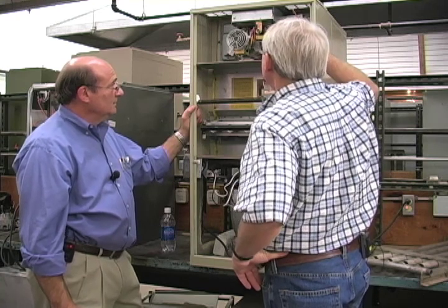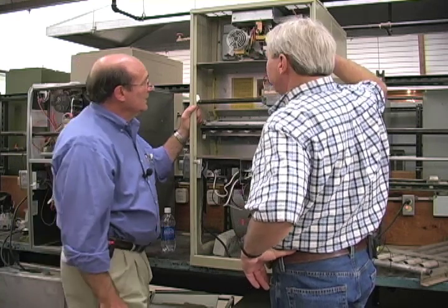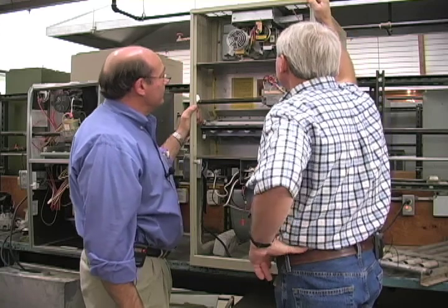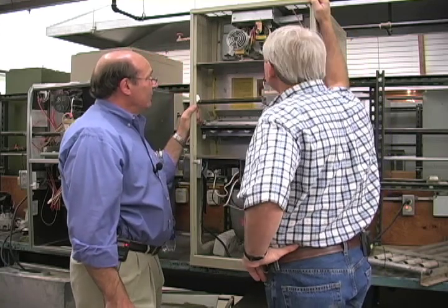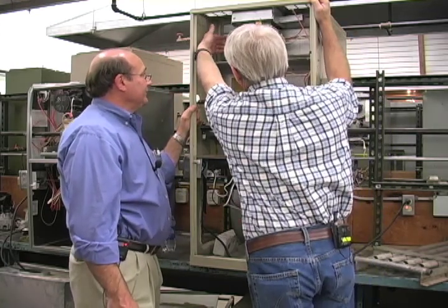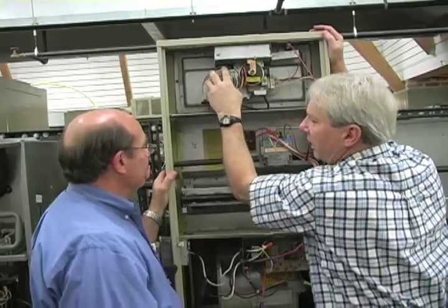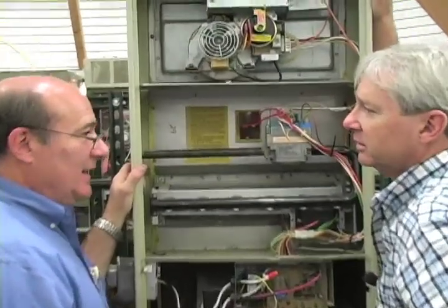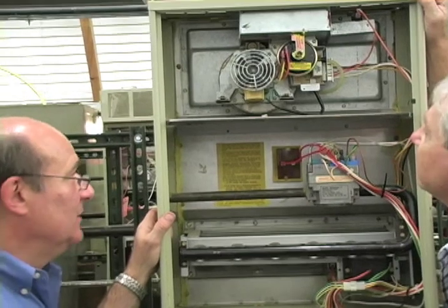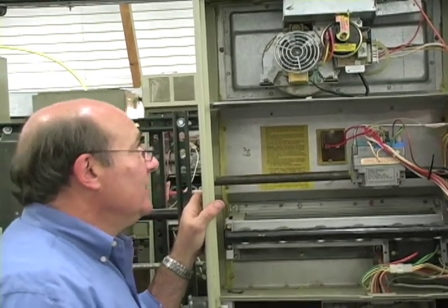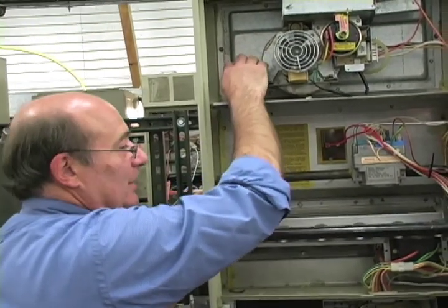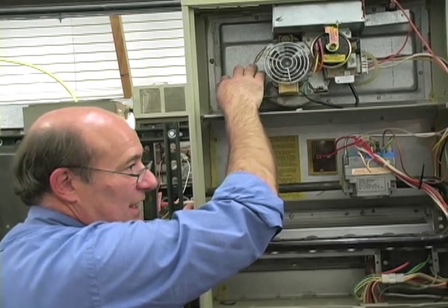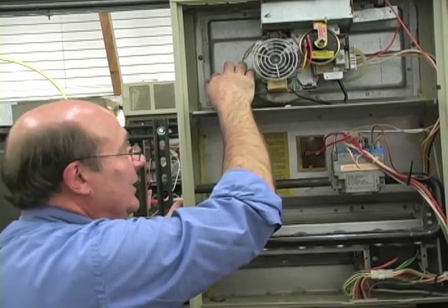One more question here. I see what looks like two fans here. I thought we were just looking at one fan that lowered the pressure in the heat exchanger. So there's a fan inside this housing, the big round housing, and there's another fan here. Oh, that fan on the outside there is just the auxiliary fan. This is what we call an air over motor. Don't forget, we're dealing with temperatures of 150 to possibly, if there's a failure, 300-400 degrees at this point.